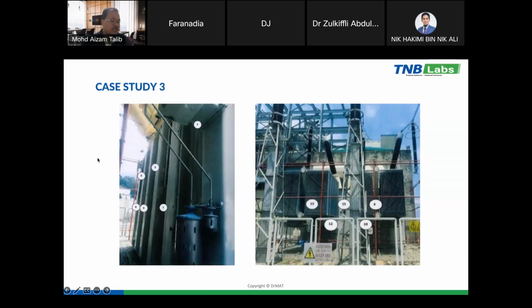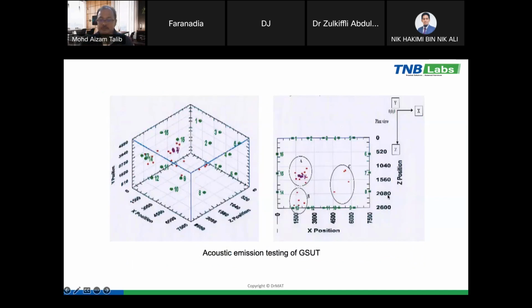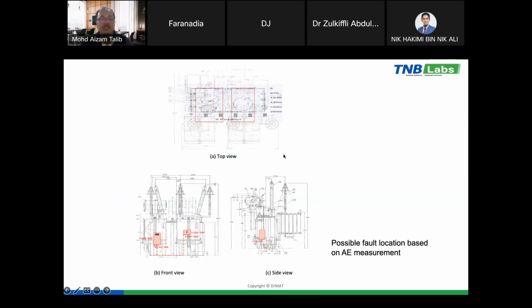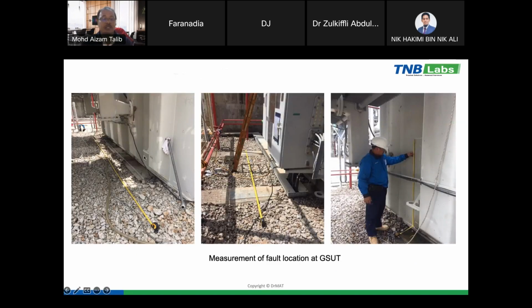And then the other case study here is a step up generator at one of the biggest IPPs in Perak. Similar issue, the gas is high. The asset owner tried to find the location of the fault so that they could do some rectification to avoid failure of the total transformer. So we put an acoustic sensor here, and then we found a few locations from our measurements. When we have the internal drawing of the transformer, we can exactly pinpoint the location of the faults. Here, we measured again the possible fault location on the generator step up unit transformer.